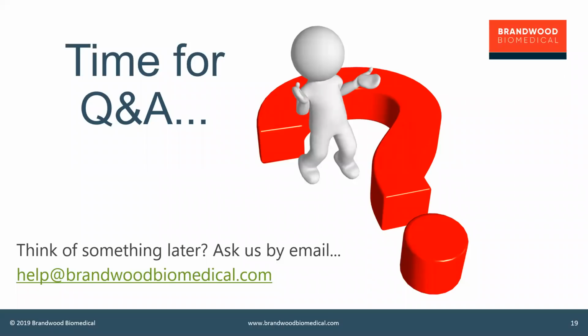Now, that being said, I think where the question really lies is if there are claims or intended uses that are either up-classified in another geography or are not something that the company wants to make in a specific geography, that doesn't mean that the DHF and the technical file changes. All it means is that in the DMR and some of the unique documents such as the IFU labeling, those may be unique. And you will have to create another product variant to show segregation of those two geographies because effectively you can't give that product.